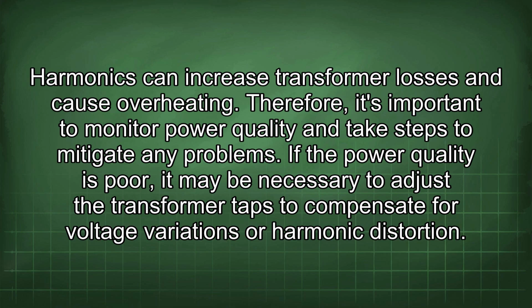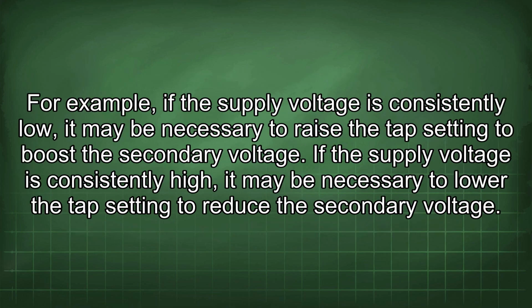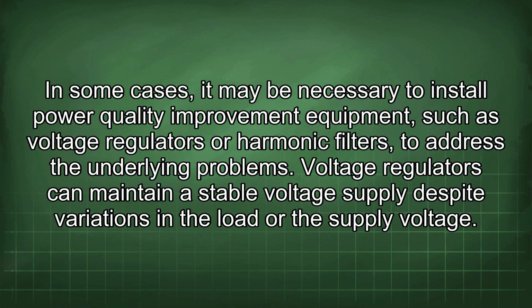If the power quality is poor, it may be necessary to adjust the transformer taps to compensate for voltage variations or harmonic distortion. For example, if the supply voltage is consistently low, it may be necessary to raise the tap setting to boost the secondary voltage. If the supply voltage is consistently high, it may be necessary to lower the tap setting to reduce the secondary voltage. In some cases, it may be necessary to install power quality improvement equipment such as voltage regulators or harmonic filters to address the underlying problems. Voltage regulators can maintain a stable voltage supply despite variations in the load or the supply voltage.